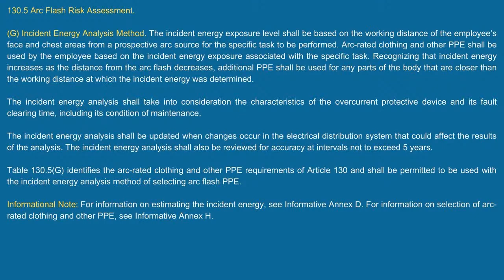All right. Now, when you get in, you look at G, this ties in with table 130.5G, and this is the incident energy analysis method. I'm not going to read all this, but basically what it's telling you is that this incident energy exposure level shall be based on what? The working distance of the employee's face and chest area from a prospective arc source for the specific task to be performed. And that's what I was saying. Most of the time you're interacting with it and they just do an arm's length, and that's 18 inches.